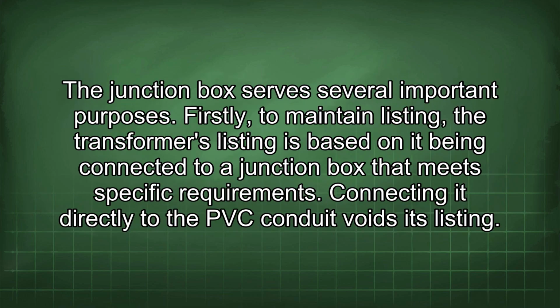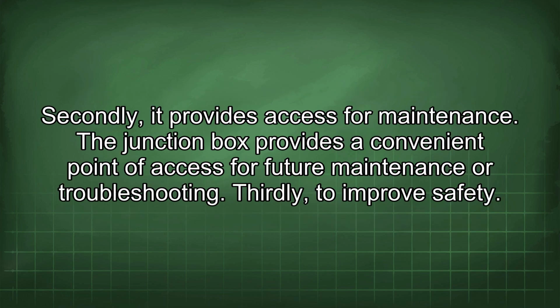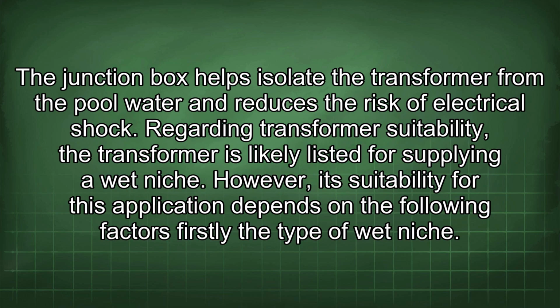The junction box serves several important purposes. Firstly, to maintain listing. The transformer's listing is based on it being connected to a junction box that meets specific requirements. Connecting it directly to the PVC conduit voids its listing. Secondly, it provides access for maintenance. The junction box provides a convenient point of access for future maintenance or troubleshooting. Thirdly, to improve safety.